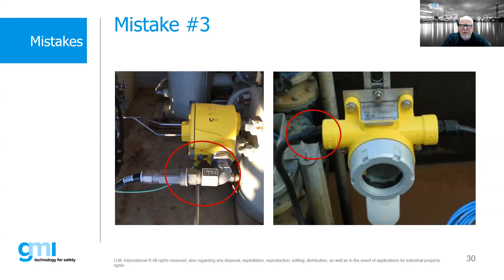The picture on the right may be an issue because we see nylon cable glands, typically used with a certified Ex e type enclosure. However, that box is actually a flame-proof enclosure. That doesn't necessarily mean the nylon glands aren't acceptable, because if the transmitter is protected by intrinsic safety, nylon glands might be fine. But generally, since it's flame-proof, we'd want to use a flame-proof gland, so that issue is also a problem we need to be aware of.